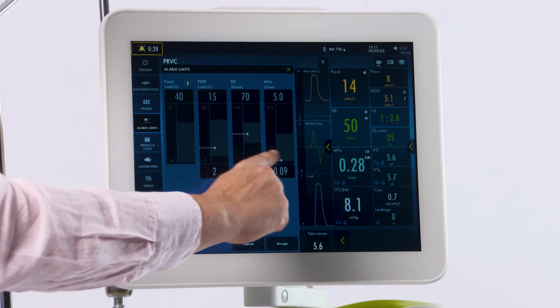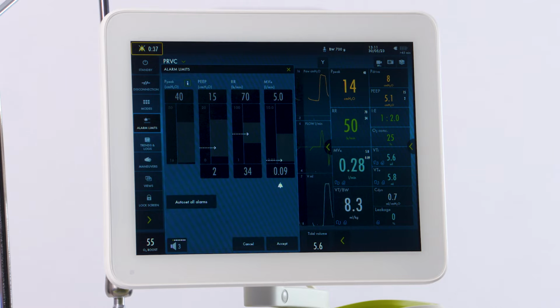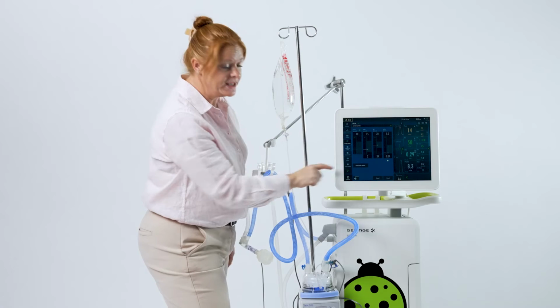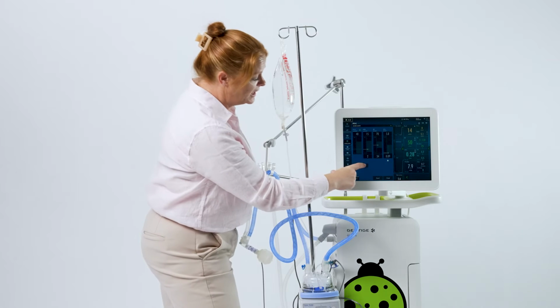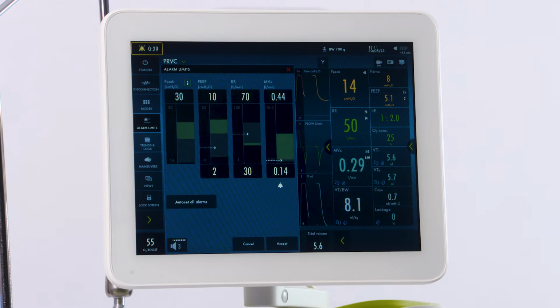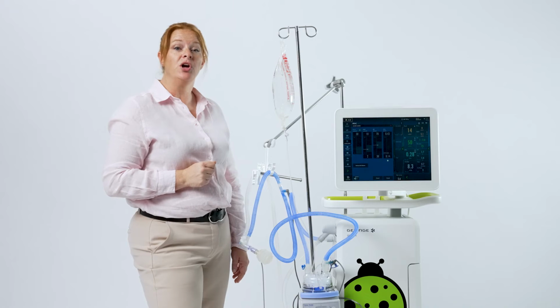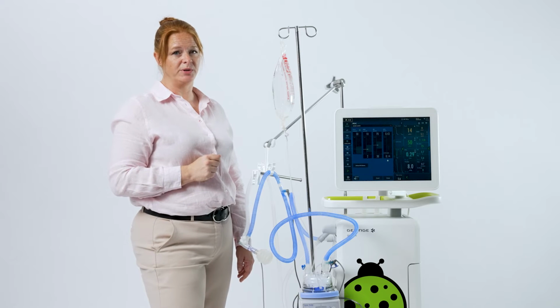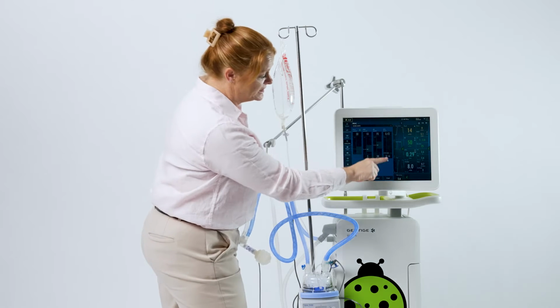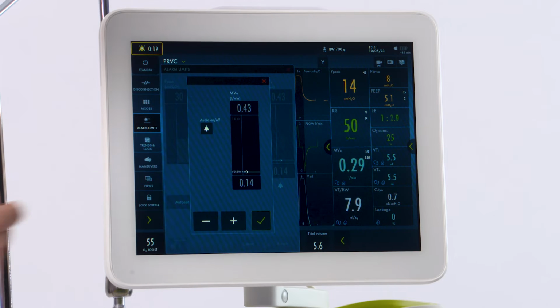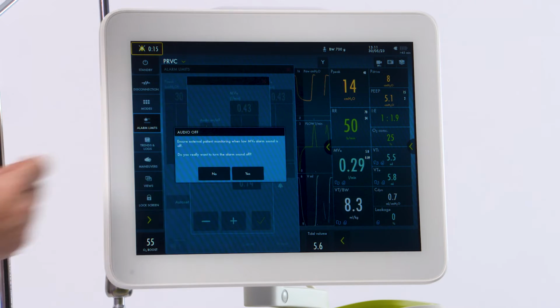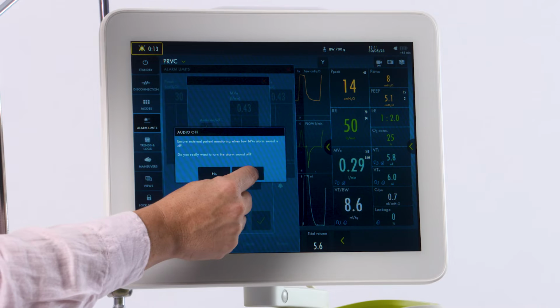Your white arrows indicate what your patient's currently doing. At the bottom is an auto set feature. If you touch it, it will automatically adjust your alarms based on what your patient is doing. You can also silence some audible alarms. For instance, here you see the bell at the bottom indicating you can silence the audible. Touch it to silence and accept.